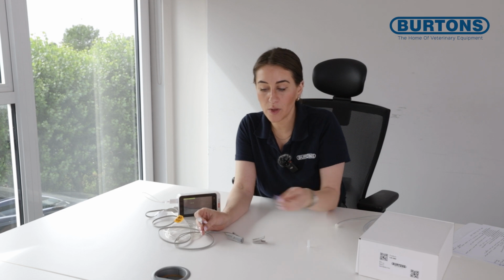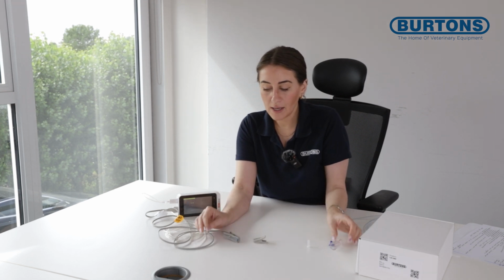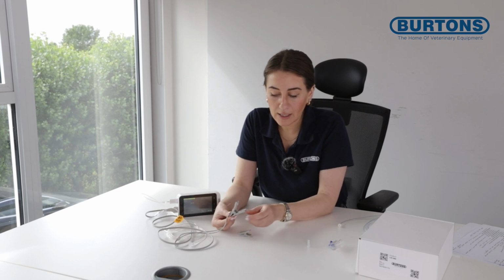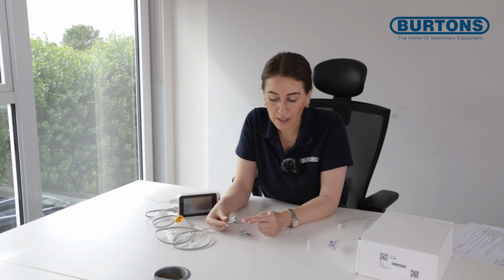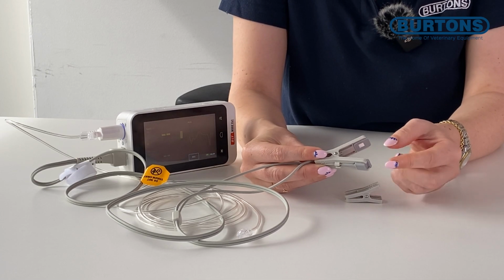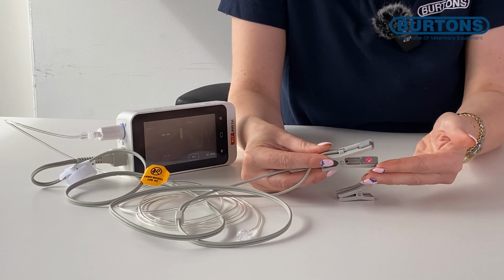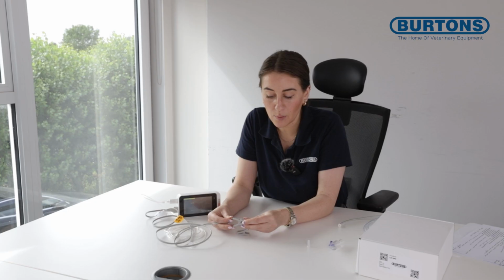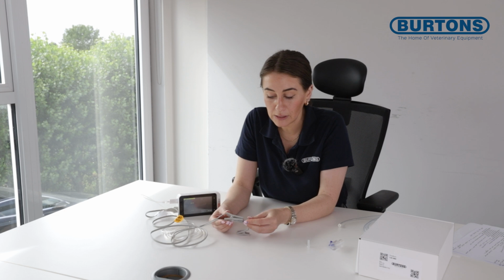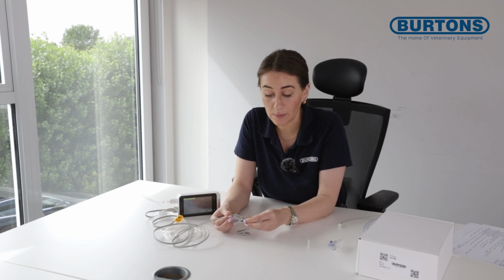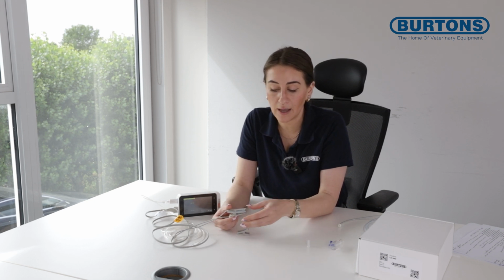In terms of practical use, we spoke already about our capnograph and how we would use it with our airway adapter, and how we'd use low dead space adapters for smaller patients. We often get a lot of questions about how to maximize the use of our SPO2 probe. We can see here that we have an infrared light, and then we've got our receiver. So essentially we're trying to put tissue in between here to allow the machine to monitor the hemoglobin and the saturation of that hemoglobin. So to try and maximize that in terms of locations, the ideal location for this probe is the tongue. Ideally we want to use it in the center of the tongue to maximize its contact with tissue.